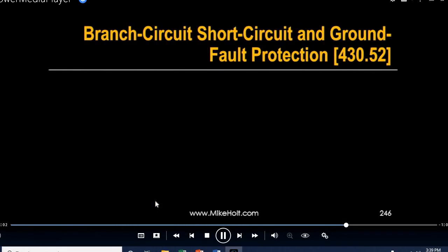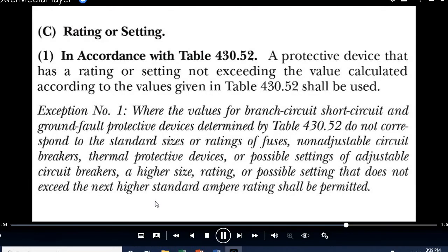So let's do the calculations in sizing the branch circuit. A protection device that has a rating or setting not exceeding the value calculated in the table shall be used. Where the values of the branch circuit short circuit and ground fault protection device determined by the table do not correspond to the standard size fuses, then we can go up to the next higher ampere size.